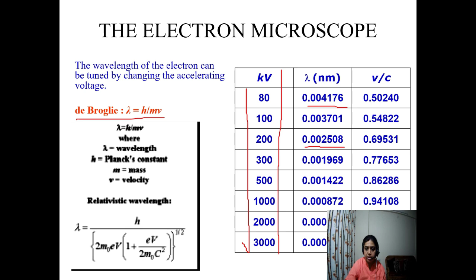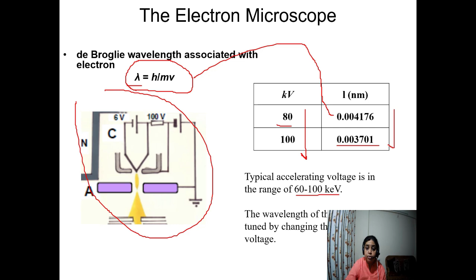So let's again come to the electron microscope. This is again the de Broglie wavelength associated with the electron. This is your typical electron gun, the source of the electrons. They are accelerated through the acceleration column. If you apply 80 kV, the de Broglie wavelength for the electron will be 0.004 nanometer. If we increase the voltage from 80 to 100 kV, it will go down to 0.003 nanometer. As a result, the resolution of the instrument is improving. The typical acceleration voltage is generally 60 to 100 kV in an SEM machine. So just by controlling the acceleration voltage, we can improve the resolution of the system.